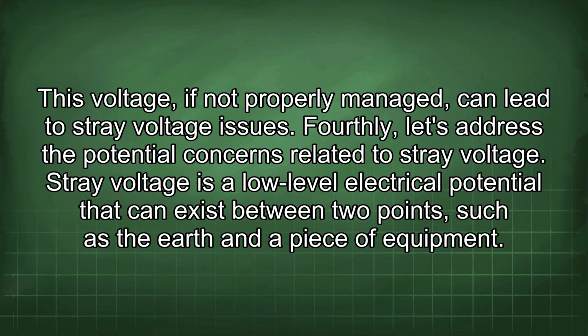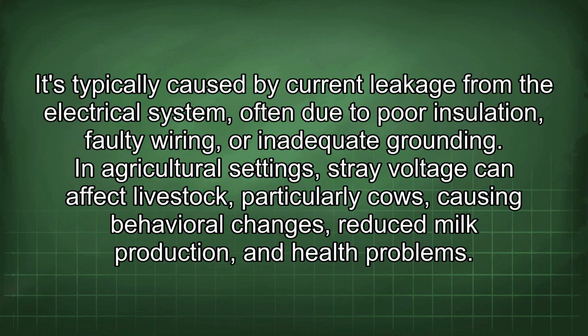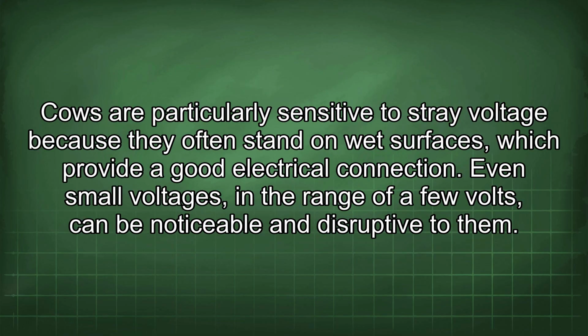Fourthly, let's address the potential concerns related to stray voltage. Stray voltage is a low-level electrical potential that can exist between 2 points, such as the earth and a piece of equipment. It's typically caused by current leakage from the electrical system, often due to poor insulation, faulty wiring, or inadequate grounding. In agricultural settings, stray voltage can affect livestock, particularly cows, causing behavioral changes, reduced milk production, and health problems. Cows are particularly sensitive to stray voltage because they often stand on wet surfaces which provide a good electrical connection. Even small voltages, in the range of a few volts, can be noticeable and disruptive to them.